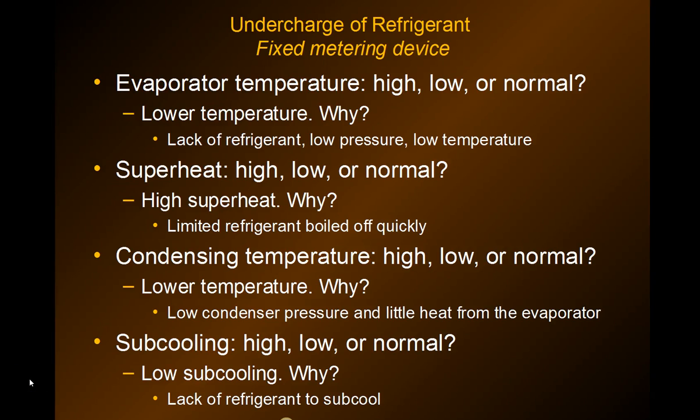Our first example is an undercharged system that's a fixed metering device with a cap tube. This happens fairly often with cap tube systems. Those are usually the small prep tables used to hold meat, deli, and produce for making sandwiches or pizzas. Ingredients are sometimes stored in canisters on top, and underneath there's a small storage area as well.